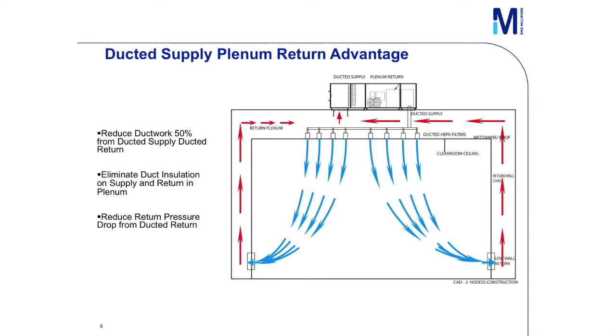A clean room is simply a box within a box. So we have an outer box and an inner box. We have our air handler on the roof. We're supplying our HEPA filters, high efficiency particle air filters, with the air from the air handler, and we're returning it through a return air wall. That's basically acting like a piece of ductwork. So we reduce cost by eliminating half of the ductwork. We use the wall as a duct. We don't build in all that extra ductwork to return the air. By doing that, you eliminate the need for duct insulation, because that space above the ceiling is all conditioned air. So you don't need to insulate that ductwork.